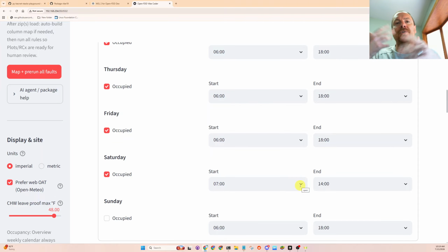they run into temperature control problems, and then they start changing this to run way longer than what is required because of extreme weather events, and then they forget about it. Pretty soon, in mild weather seasons, for months at a time, you're still running the building for hours at a time.